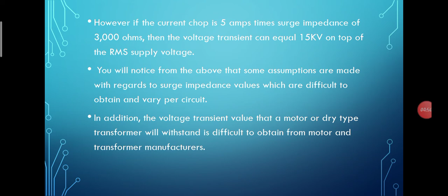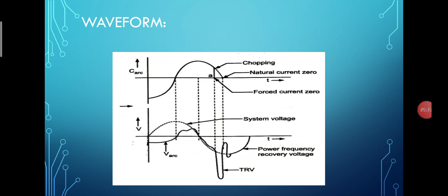In order to reduce the phenomenon of current chopping, the voltage has to be reduced. This is possible by connecting voltage grading resistors across the circuit breaker's contacts during interruptions. In medium voltage systems, an RC surge absorber is connected across line and ground in between the inductive load and the circuit breaker. As a result, the RC combination absorbs the overvoltages.